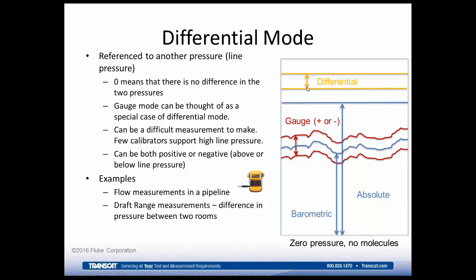As I said, gauge mode can be thought of as a special case of differential mode, where the line pressure is atmosphere. While we say that gauge mode is pretty easy, differential mode can be much more difficult, especially in the case of a high line pressure, where the pressure that you're comparing against is much higher than your differential pressure. An example of that situation is a flow measurement in a pipeline. The overall line pressure of the pipeline may be a couple of thousand psi.